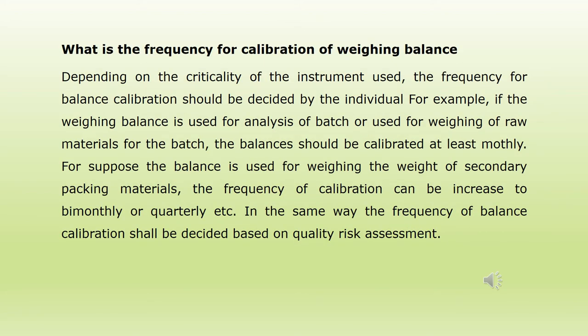What is the frequency for calibration of a weighing balance? Depending on the criticality of the instrument use, the frequency for balance calibration should be decided. For example, if the weighing balance is used for analysis of a batch or for weighing raw materials, the balance should be calibrated at least monthly. If the balance is used for weighing secondary packing materials, the frequency can be increased to bimonthly or quarterly. The frequency shall be decided based on quality risk assessment.